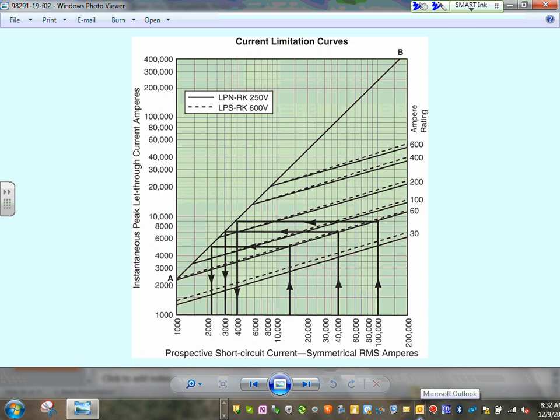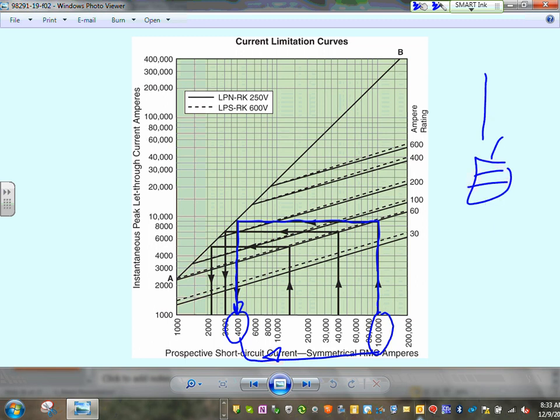Current limiting, if you have a current limiting fuse, I'm going to talk about this one a little bit, guys. Look at this. I have a 100,000 amp fault. If I have a current limiting fuse, look what happened. It takes this current, takes it all the way back to this current limiting fuse size and drops it down. It drops it down to, in this case, 4,000. Can you see what a current limiting fuse is? It opens so fast that, like I said here, here's my equipment, and I have a short circuit coming. My short circuit right at this point is 100,000 amp. As it moves through this, it will drop down to 4,000 amp.